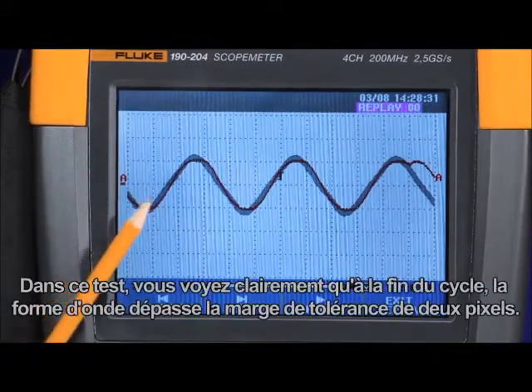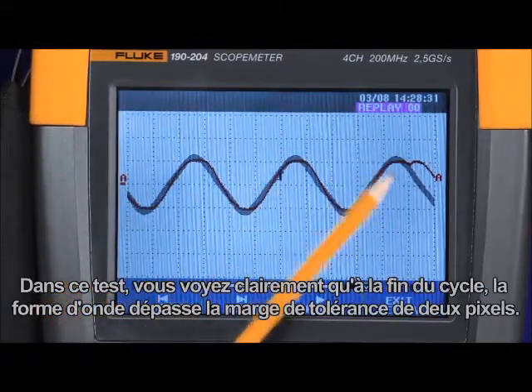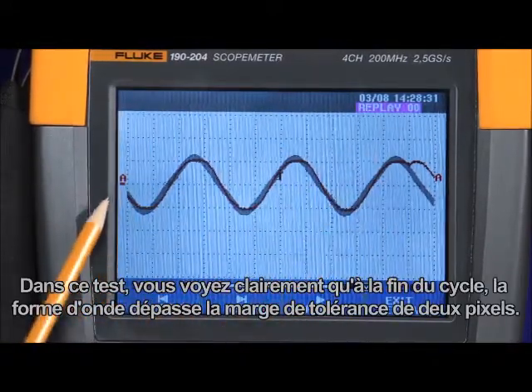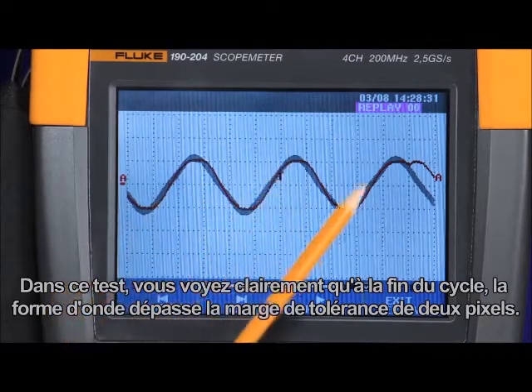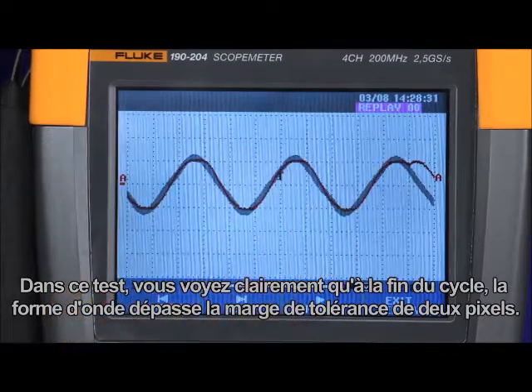Immediately you can see the gray envelope overlaid with the waveform trace the scope has captured. In this test, you can see clearly that at the end of the cycle, the waveform exceeded the two pixel tolerance window.